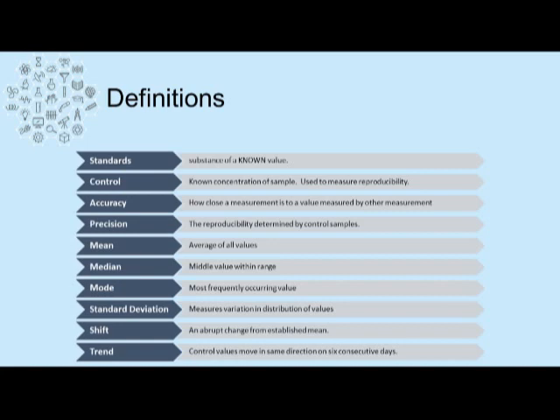Standard deviation measures the variation and distribution of values. A shift is an abrupt change from an established mean. A trend is when control values move in the same direction for six or more days.